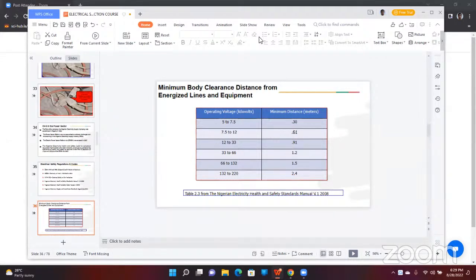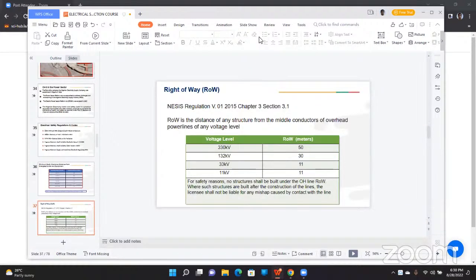From 5 to 7.5 kilovolts, you need a minimum of 0.30 meters body clearance. For 7.5 to 12 kilovolts, it's 0.61 meters; 12 to 33 kilovolts, 0.91 meters; 33 to 66 kilovolts, 1.2 meters; 66 to 132 kilovolts, 1.5 meters. Now we move to what we call right of way.